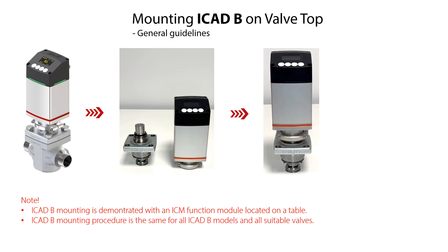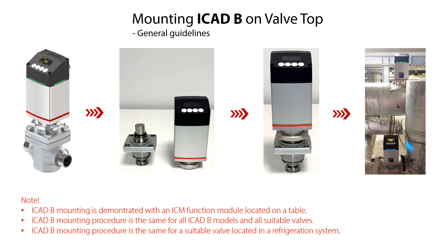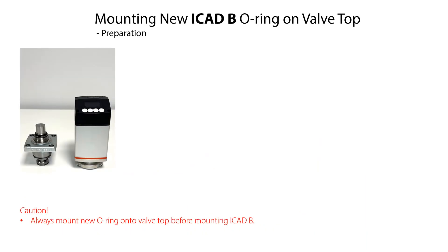However, as already mentioned, the mounting procedure is the same for all ICAD B models and all suitable valves, and the mounting procedure is the same with the valve already located in a refrigeration system. Before mounting the ICAD B on the valve top, we firstly need to mount the new o-ring onto the valve top.